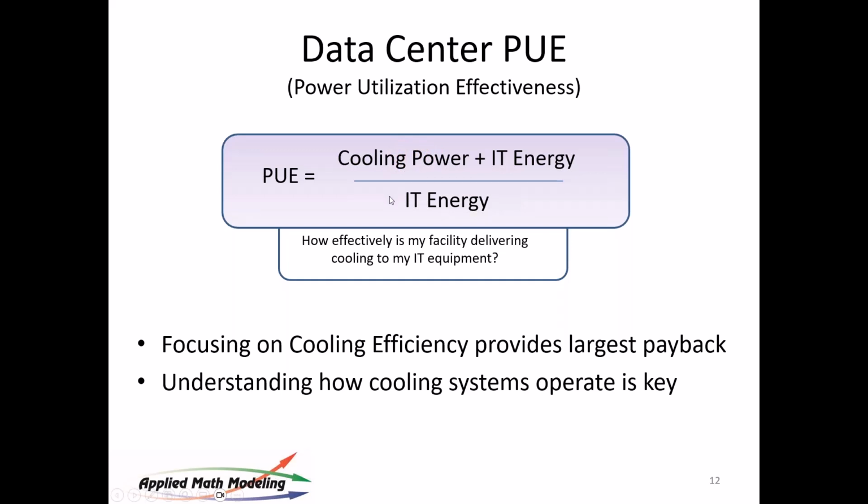In fact, if you had a PUE of 2, it would mean that you've got 1 here and 1 here compared to that, and that means the cooling power is equivalent to the IT energy power. Maybe we should mention here, Paul, that as most of you probably know, PUE was invented by the Green Grid, but they have now handed over to ISO, an international standards organization, and PUE is now an ISO standard, actually.